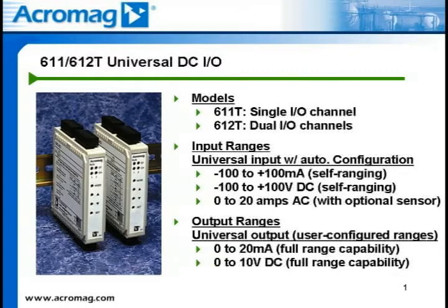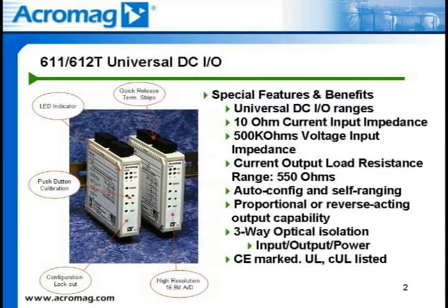Output ranges can be configured for 0 to 20 milliamps DC or 0 to 10 volts DC with full range capability. The broad input and output ranges offer flexibility for panel shops and end users for many different application requirements. In the current input mode, the loop burden is a very low 10 ohm impedance. This makes these isolated transmitters ideal for tapping off, in series, an existing 4 to 20 milliamp loop to add a measuring or monitoring instrument.